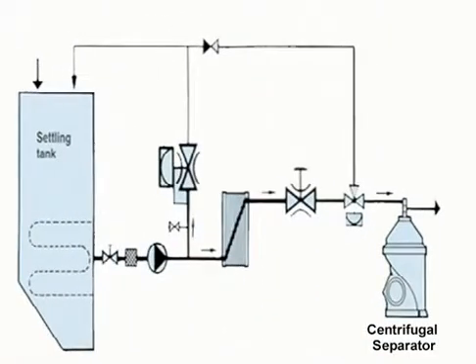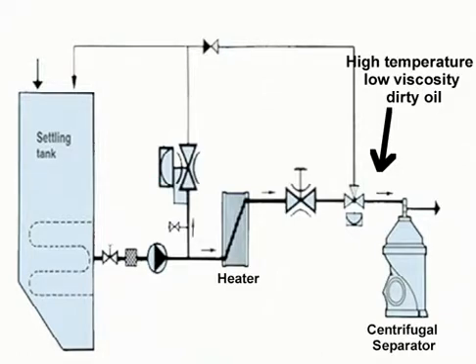Before entering the centrifugal separator, the dirty oil passes through the heater, which reduces its viscosity by increasing the temperature. The lower the viscosity, the easier it is to remove impurities from the dirty oil.